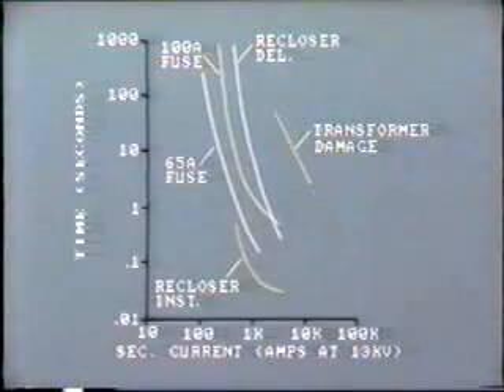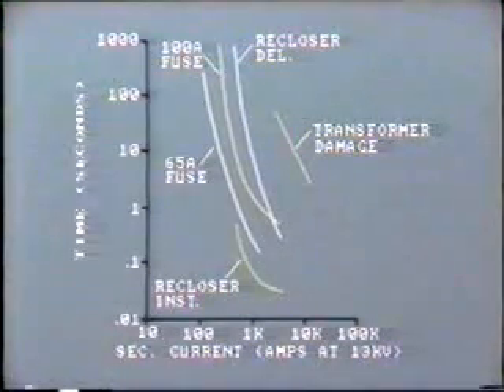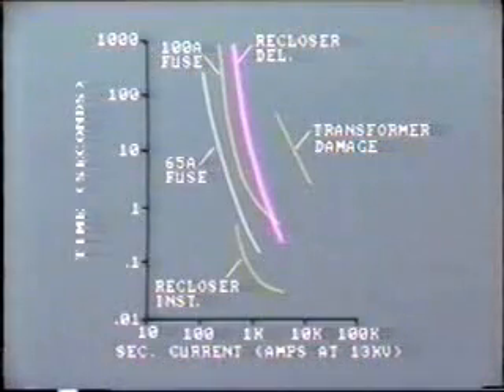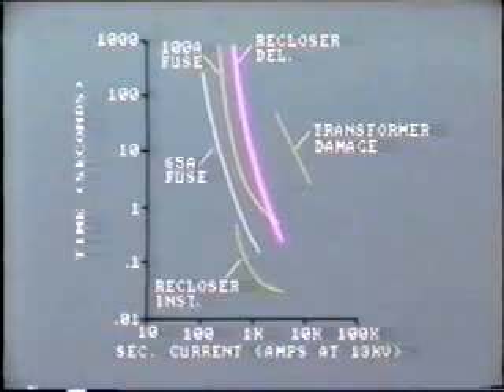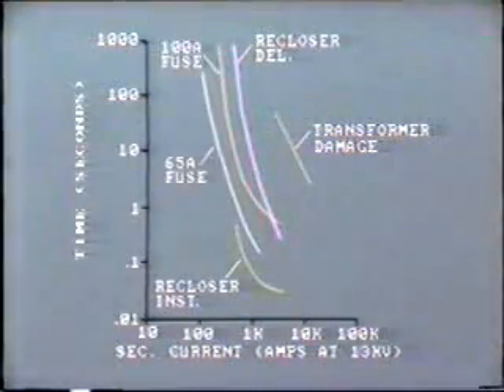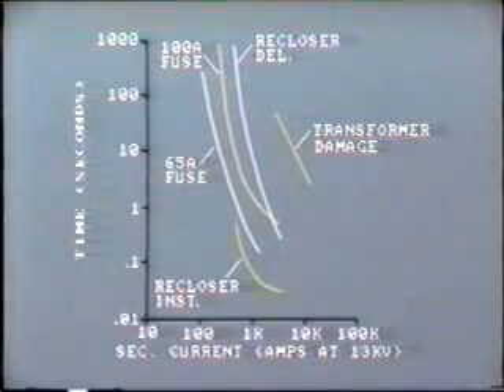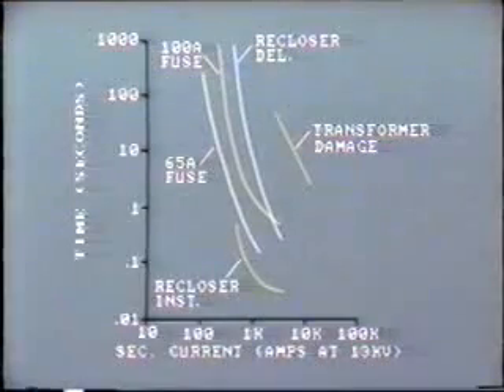The curve is shown here. Now the pattern becomes clear. The recloser still operates in good time to protect the transformer, but it allows the fuses to operate first for downstream faults. If the fuse does not clear a permanent fault, then the recloser will remain open after the third trip and so protect the transformer.